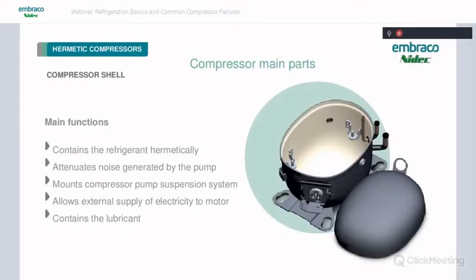So one of the main parts, of course, of the hermetic compressor is the shell. And it has a simple job, but basically it's hermetically sealed, so it contains the refrigerant, contains everything inside the system. But one of the things it does, it also attenuates the noise generated by the pump. And Embraco and other manufacturers spend a lot of time designing this shell to keep the noise generated by the pump as quiet as possible. But it also mounts the suspension system. It allows for external supply of electricity to the motor and contains the lubricating oil.